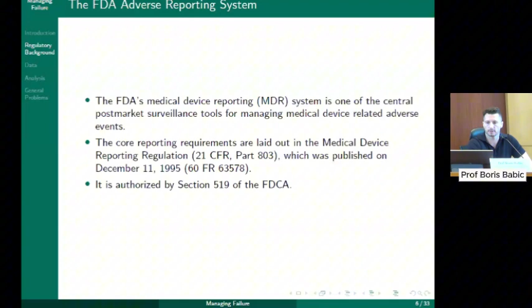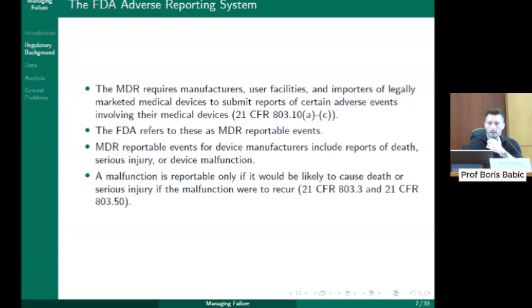Some of the key requirements are all in the FDCA, and it requires manufacturers, user facilities, and importers of legally marketed medical devices to submit reports of certain adverse events. FDA refers to these as MDR reportable events. These include reports of death, injury, or malfunction. And a malfunction is reportable only if it would be likely to cause death or injury.